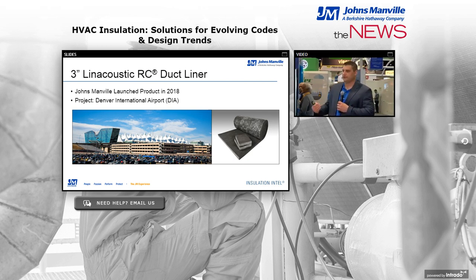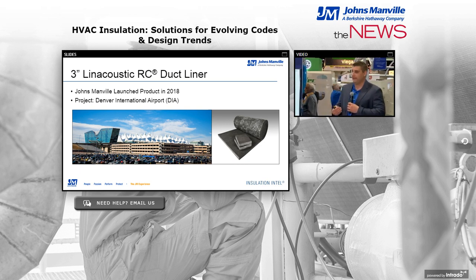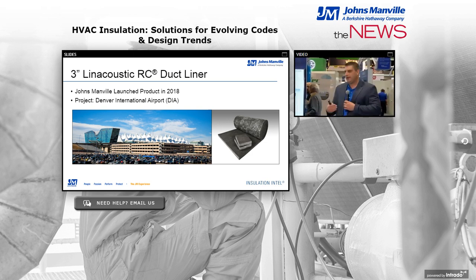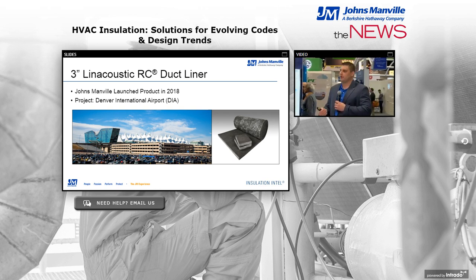One of our customers had a request at the Denver International Airport. Johns Manville is based out of Denver, so we go in and out of this airport a lot. The DIA expanded their parking garage—a large expansion you can see here in the forefront. One of our customers came to me and said, we really need an R12 duct liner application. We don't want a double layer of two R6s or three R4s, or a 2-inch and a 1-inch material to reach this. We want one step, one process we can put in place and let the whole thing happen just as we would with a regular liner job.